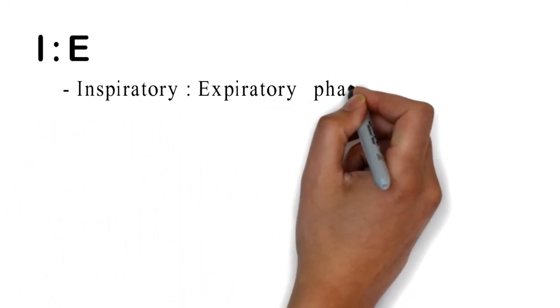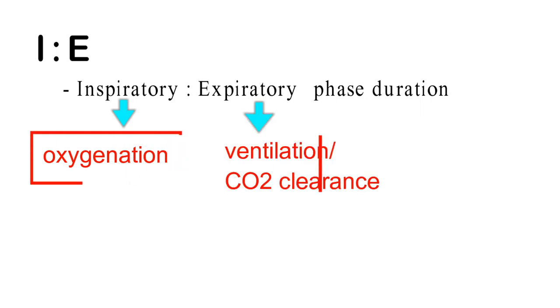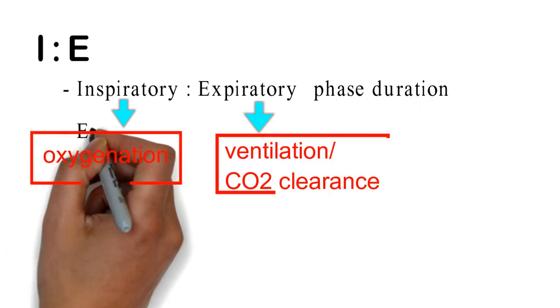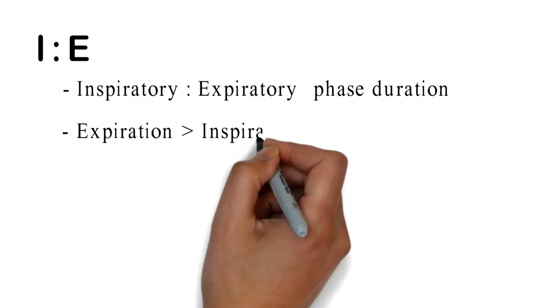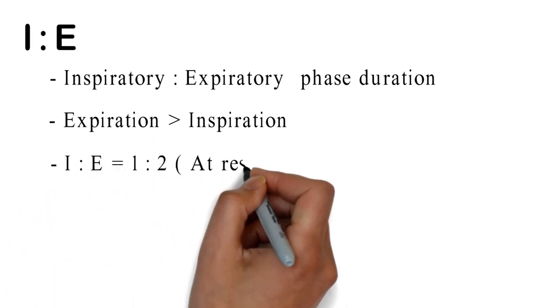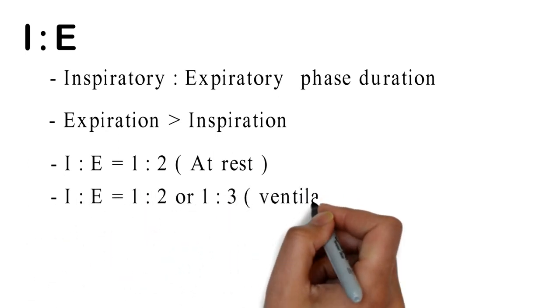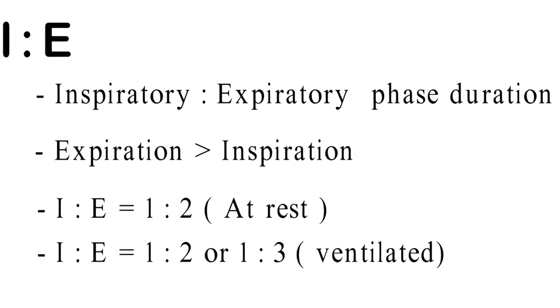IE ratio is the ratio of duration of inspiratory phase to expiratory phase. Inspiration helps in oxygenation whereas expiration helps in CO2 clearance or ventilation. Normally expiration is longer than inspiration. At rest, inspiration to expiration duration is 1 to 2. We can set I to E from 1 to 2 to 1 to 3 for a ventilated patient.